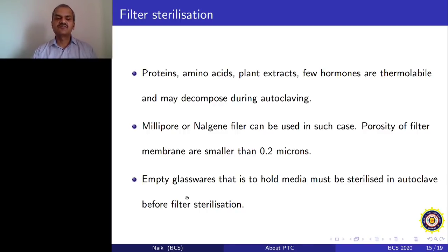So obviously you need an empty glassware to hold the media after sterilization, because while sterilizing, on the other side, because of gravity, the filtrate comes downward into a glass vessel. Now that glass vessel has to be autoclaved before filter sterilization. So the equipment or glassware, whatever you need during filter sterilization, or even these Nalgene filters and their cabins and their entire assembly, has to be autoclaved. Okay, you don't have to autoclave the filters, but the assembly has to be autoclaved.